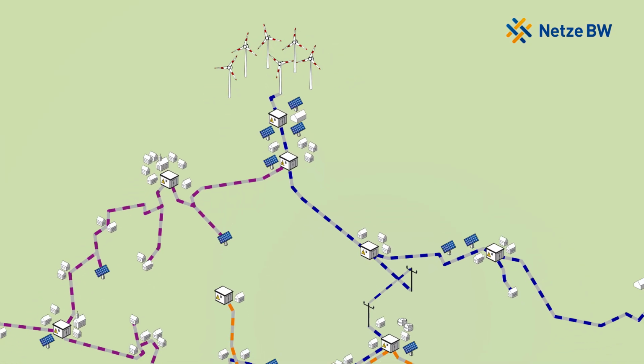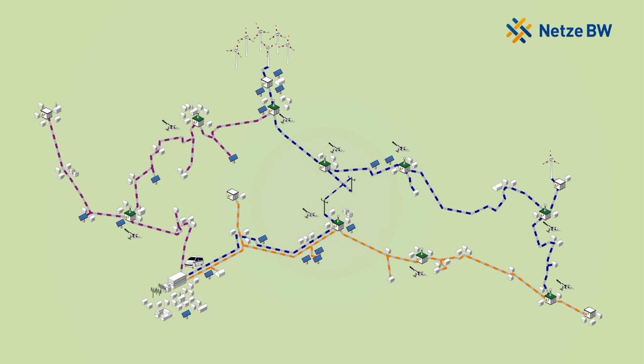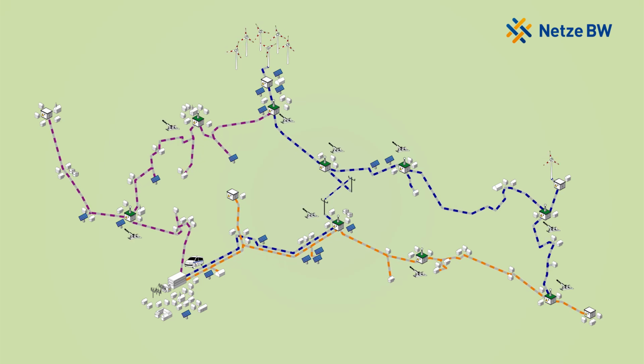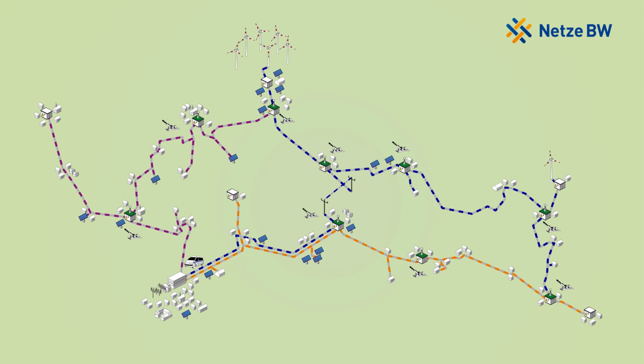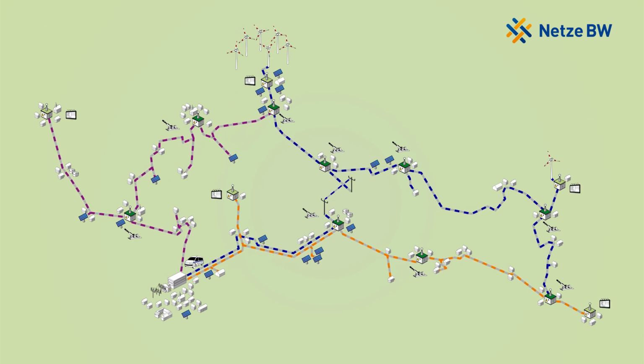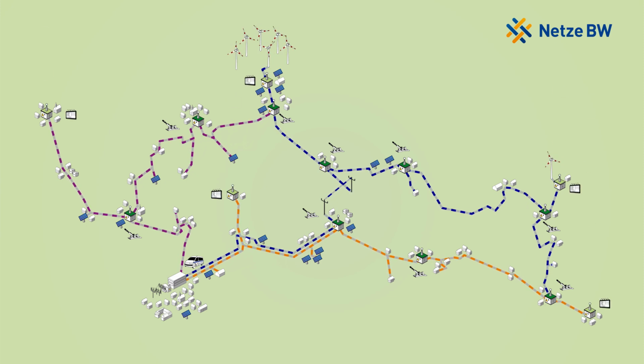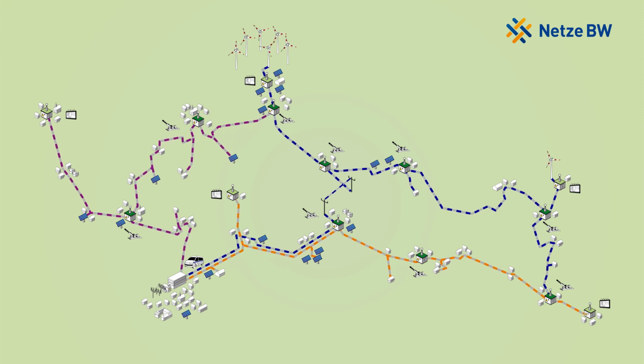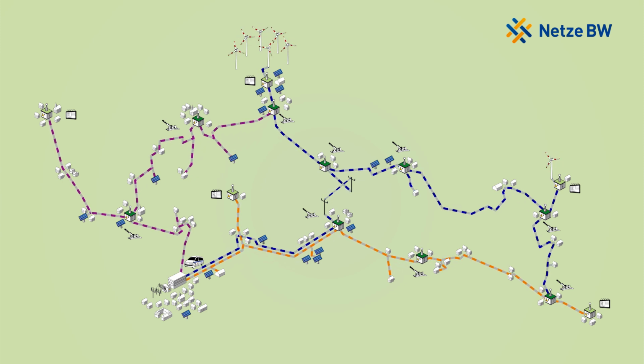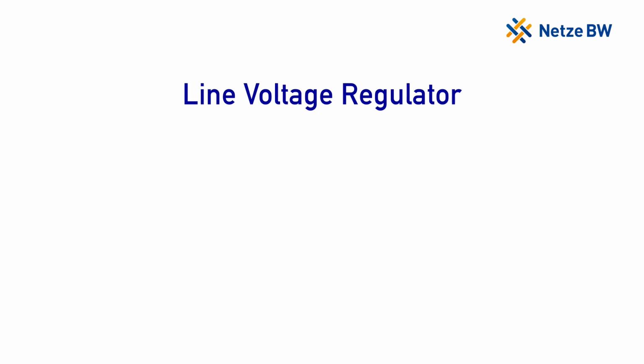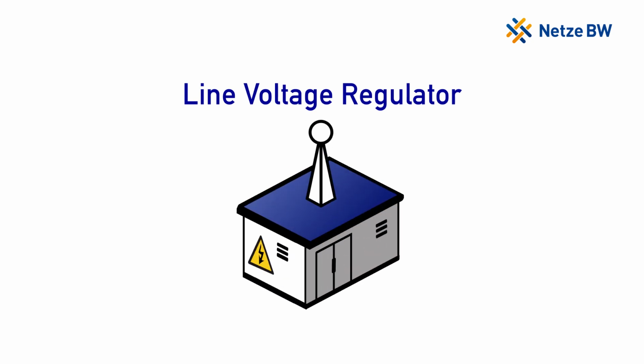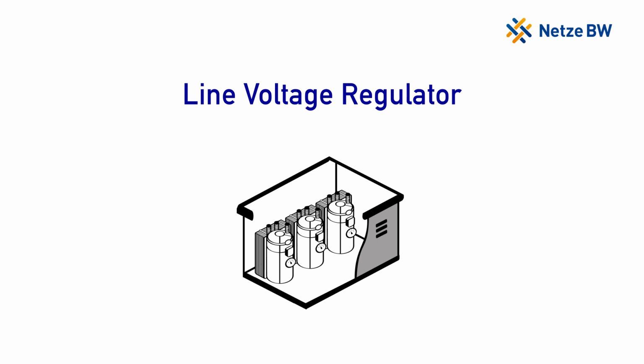Within the local Niederstetten network, such intelligent substations are placed at 9 strategically important locations. In addition, measuring instrumentation has been installed at the ends of each medium voltage line where the highest and lowest voltage levels generally occur. With the help of the line voltage regulators, the voltage level in the downstream grid will be adjusted according to the given situation.